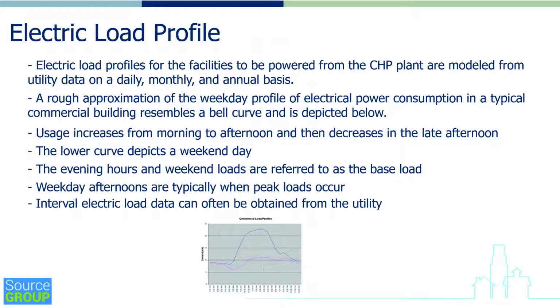Electric load profile. Electric load profiles for facilities to be powered from CHP plants are modeled from utility data on a daily, monthly, and annual basis. A rough approximation of a weekday profile of electric power consumption in a typical commercial building, depicted below, resembles a bell curve. The usage increases morning to afternoon and then decreases in the late afternoon. The lower curve depicts a weekend day. The evening hours and weekend loads are referred to as the base load. Weekday afternoons are typically when peak loads occur.